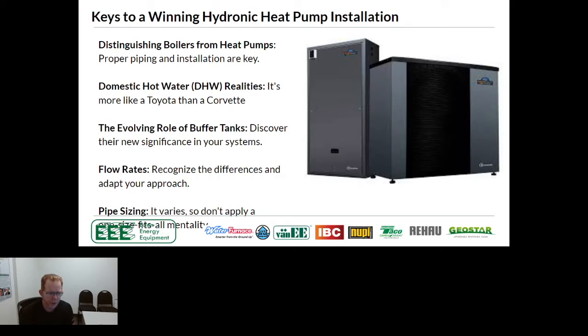We need to make sure that we can produce enough hot water with the limitations of the equipment. The other thing that's really important to keep in mind is that buffer tanks on hydronic heat pumps are very important. Some of the equipment we're going to talk about today, you don't need a buffer tank, and there are very specific technical reasons why. In other scenarios, you absolutely need to have a buffer tank. And if you don't put a buffer tank on a boiler, typically what we'll see is the boiler will short cycle.